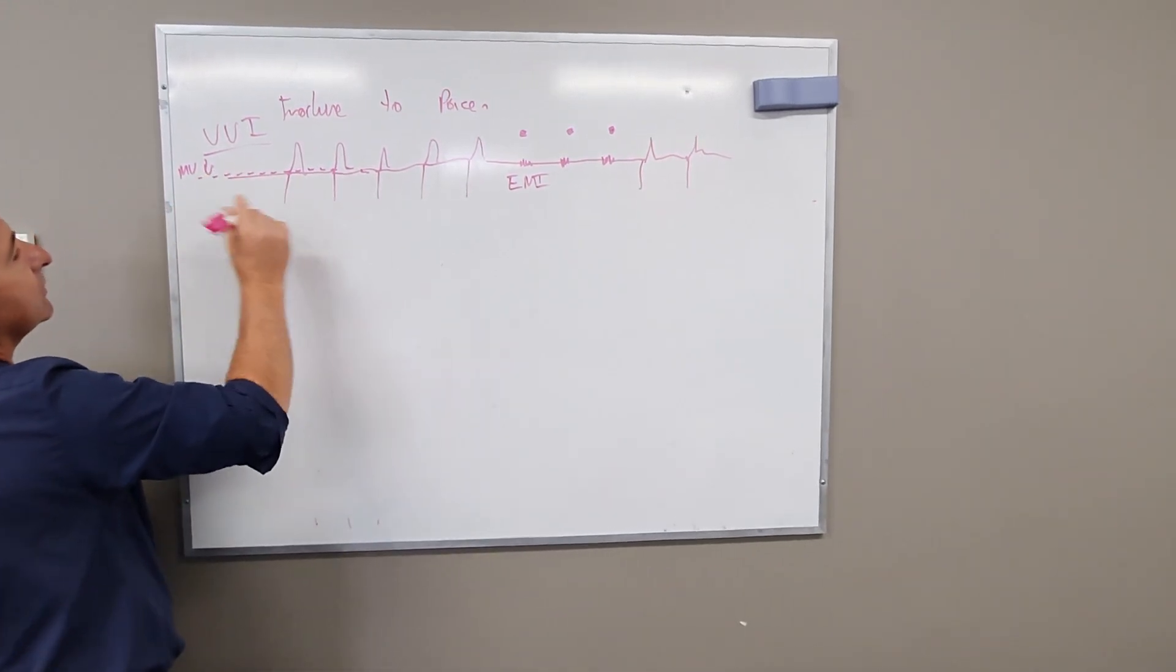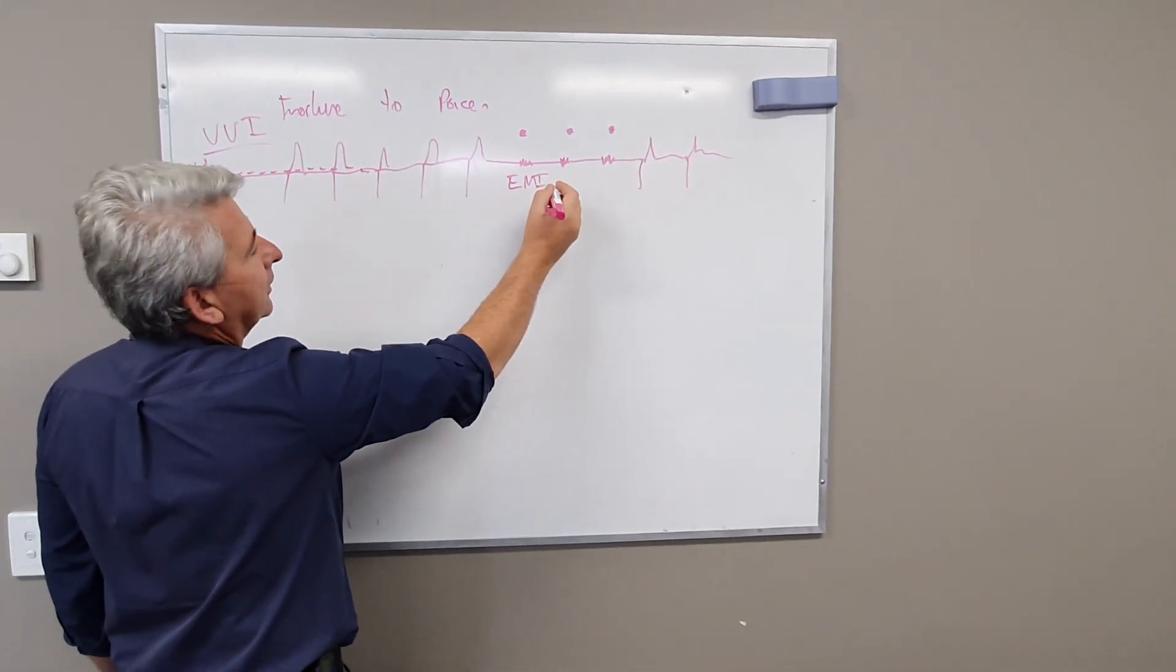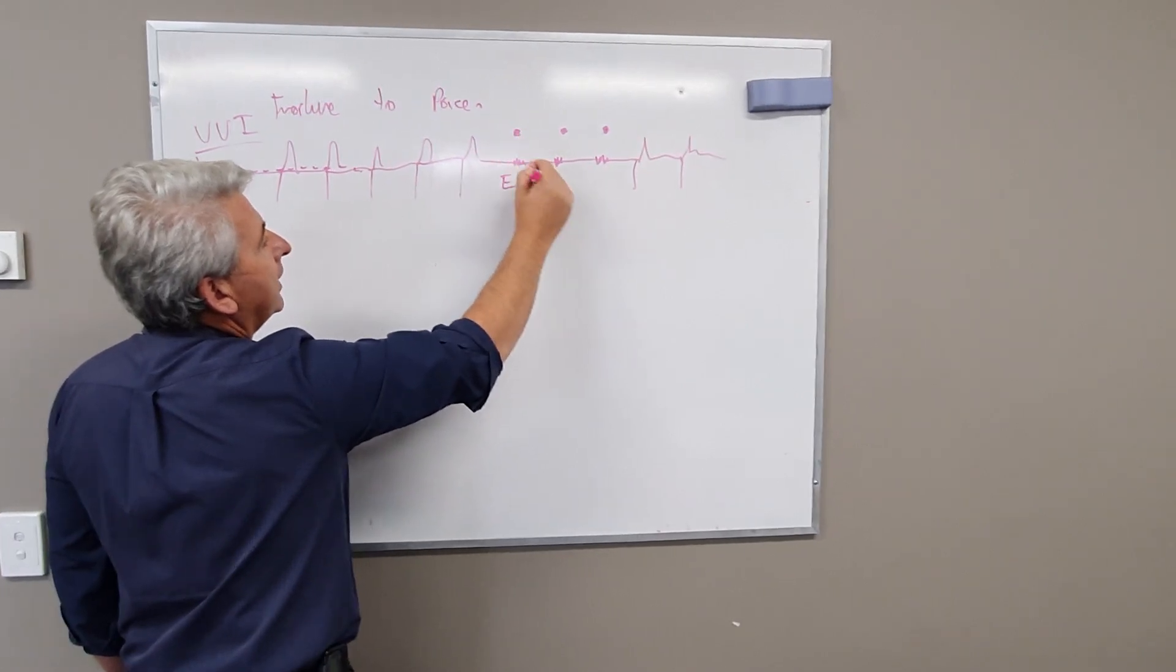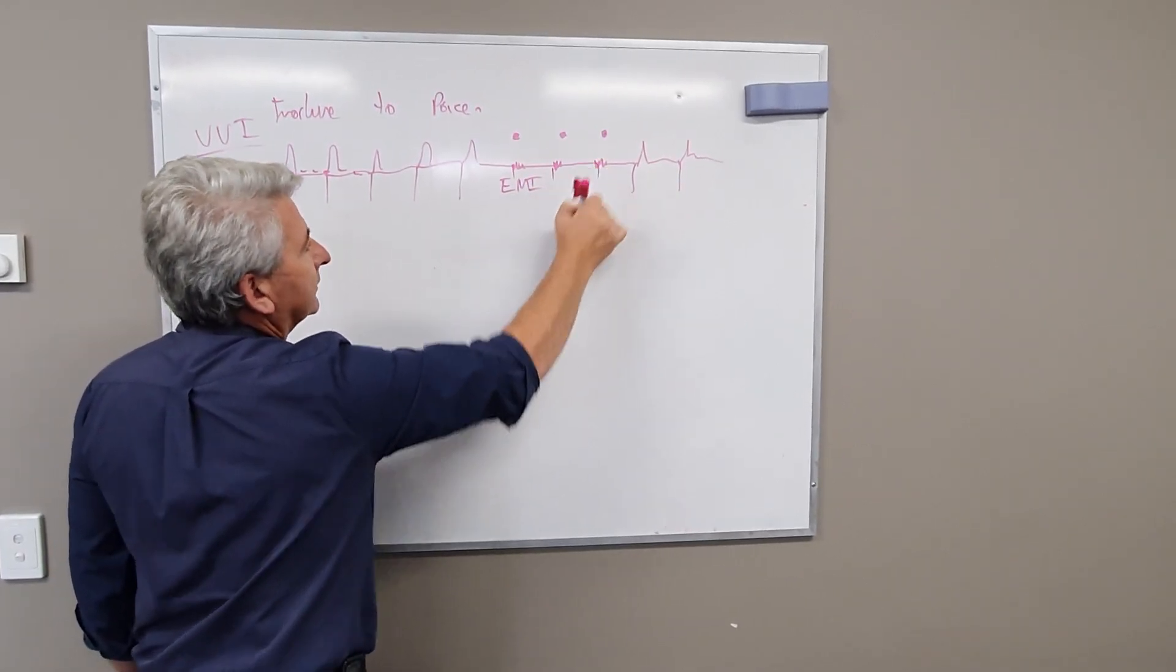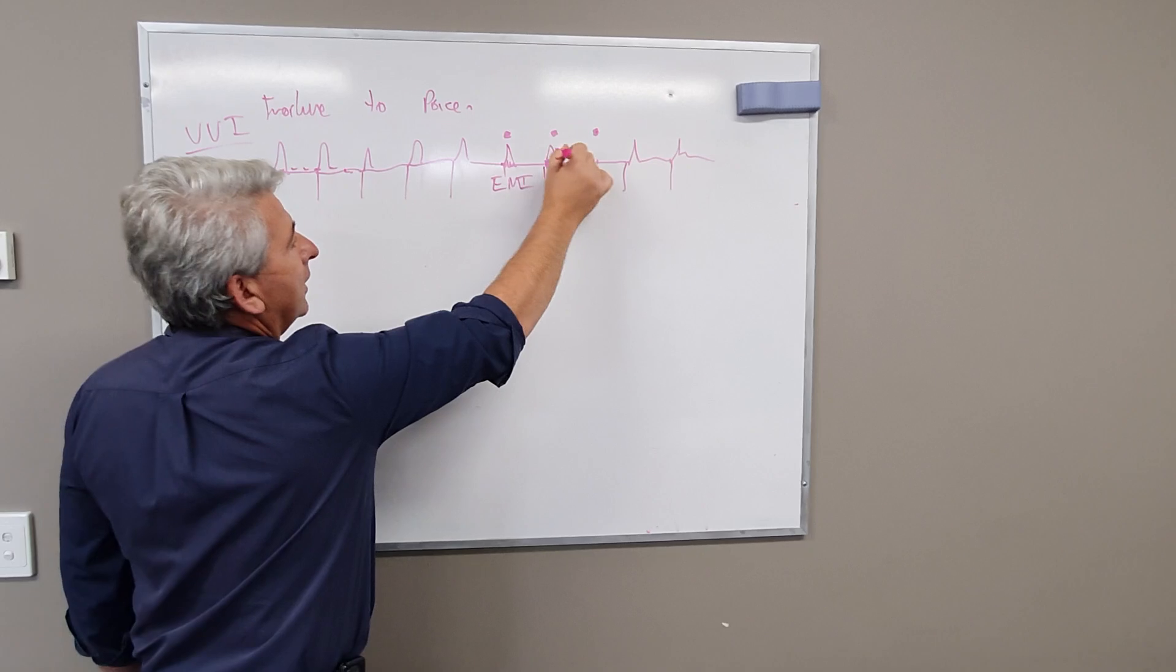How do you fix it? You just need to bump up the millivolts, and in essence what you're going to do is bring that off the line, and it'll actually start to pace, and it will be followed by a mechanical capture, and you'll have blood pressure.